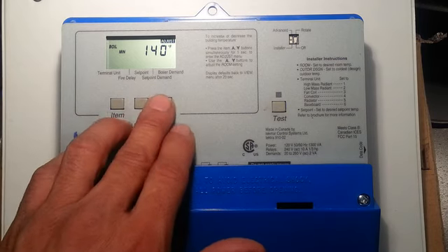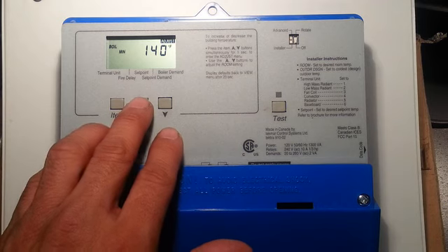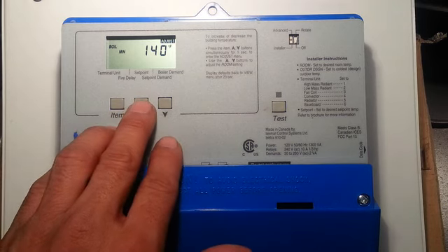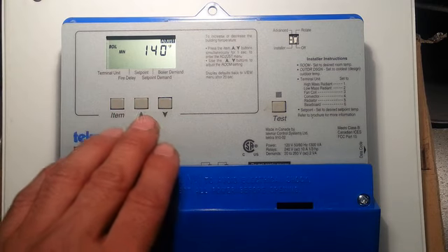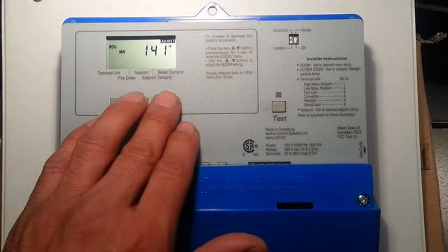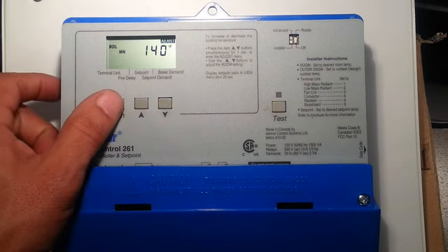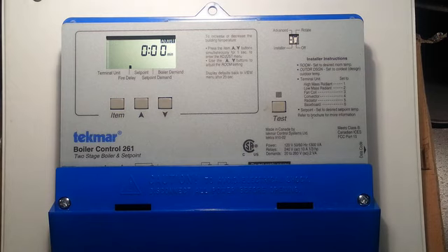Copper tube boilers are the same. If they condensate, there's a green buildup that will occur on the copper. That buildup will then plug up the tight fins, and then it will carbon up, and then it will be plugged up. So we maintain a minimum temperature of 130 to 140 depending on the type of boiler that you have.